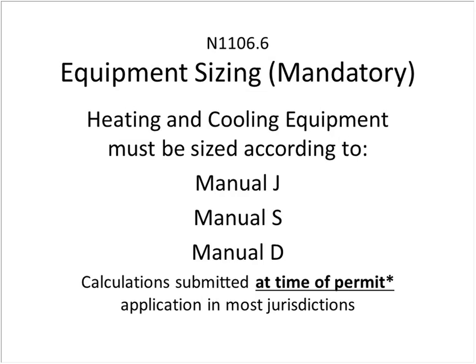This is another mandatory requirement. This has to do with heating and cooling equipment. It must be sized according to manuals J, D, and S. And manual J is to size the equipment. Manual D is to size your ductwork and how many supplies are needed in each area to get the required amount of BTUs in there. And manual S is the selection of the equipment.